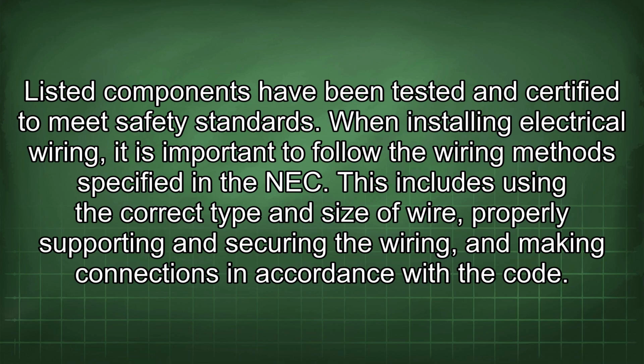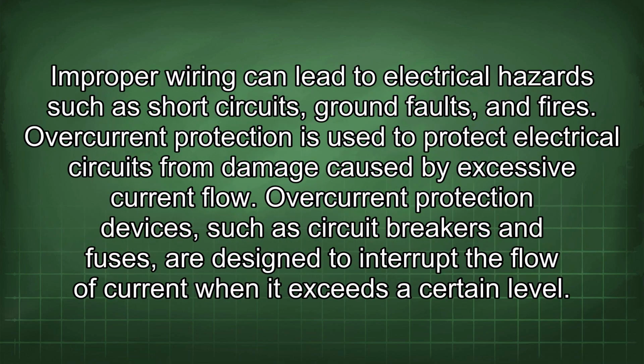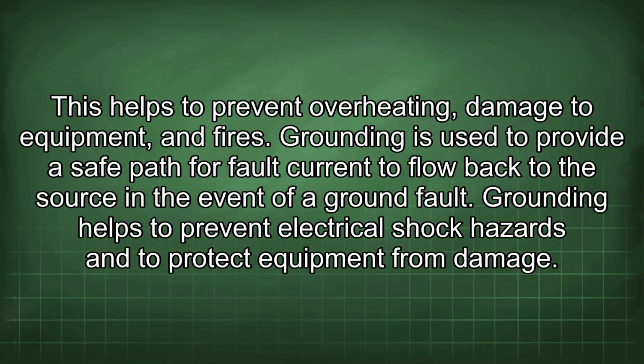When installing electrical wiring, it is important to follow the wiring method specified in the NEC. This includes using the correct type and size of wire, properly supporting and securing the wiring, and making connections in accordance with the code. Improper wiring can lead to electrical hazards such as short circuits, ground faults, and fires. Overcurrent protection is used to protect electrical circuits from damage caused by excessive current flow. Overcurrent protection devices, such as circuit breakers and fuses, are designed to interrupt the flow of current when it exceeds a certain level. This helps to prevent overheating, damage to equipment, and fires.